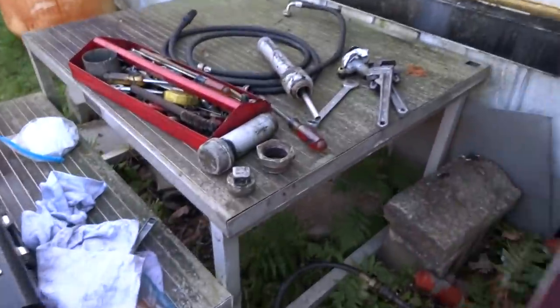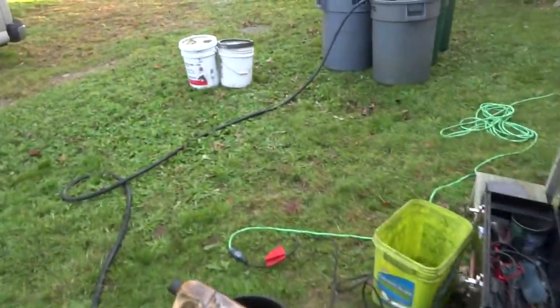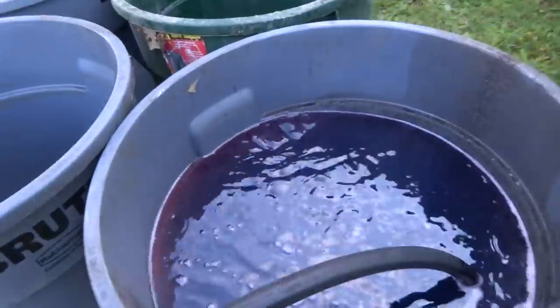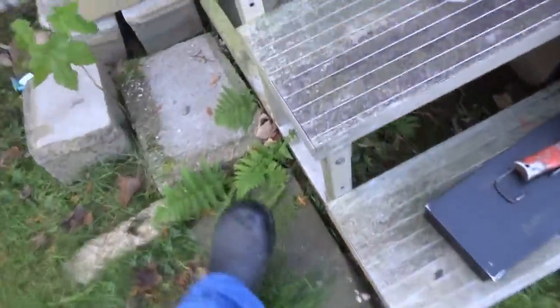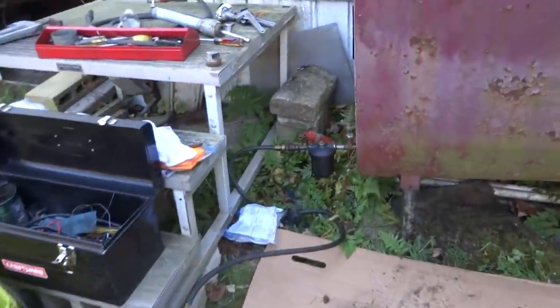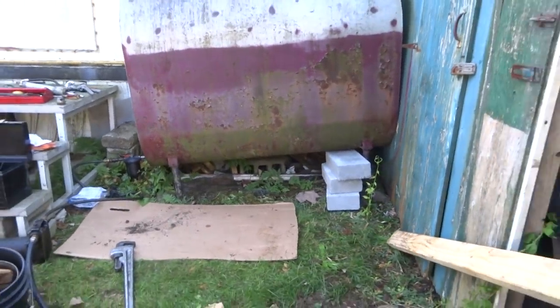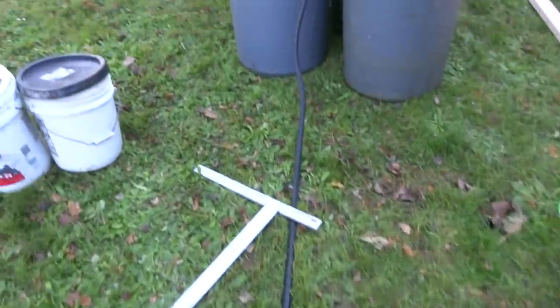I got the vent alarm off and there's a little bit of oil in there. He's running regular oil, not kerosene. I told him it's going to run kerosene. I'm trying to get as much oil out; I got a new filter in there. Probably going to have to run out and get some stone or something, because there's all kinds of mess back there. Won't know until we get it out.